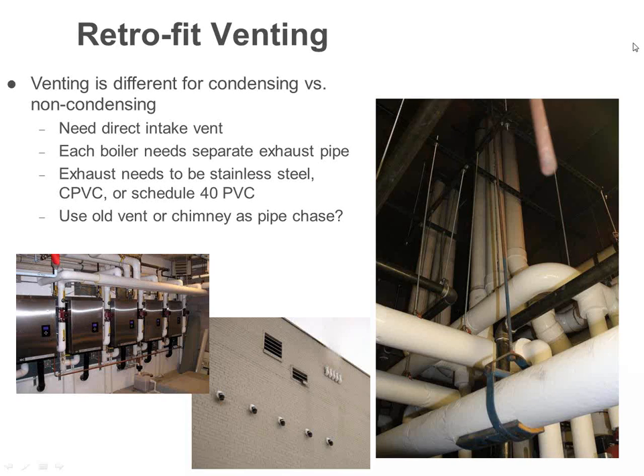Every one of these condensing boilers is going to need its own dedicated piping as well. Generally speaking, you cannot share chimneys and exhaust stacks between condensing boilers. They have inducer motors that run at reasonably high pressures, and if you have two of them on the same vent pipe, one of them will backfeed into the other. So if you see over here on the bottom left, we've got 5 boilers in this drawing. We've got 5 intake pipes and 5 exhaust pipes. Everybody gets their own pipe.